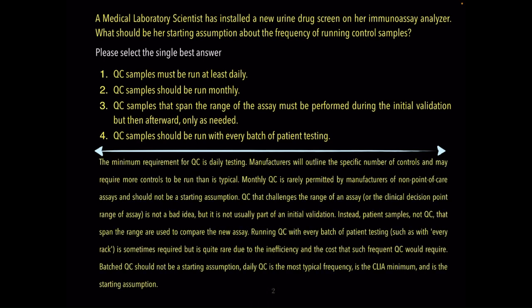The correct answer. The minimum requirement for QC is daily testing. Manufacturers will outline the specific number of controls and may require more controls to be run than is typical. Monthly QC is rarely permitted by manufacturers of non-point-of-care assays and should not be a starting assumption. QC that challenges the range of an assay, or the clinical decision point range of assay, is not a bad idea, but it is not usually part of an initial validation. Instead, patient samples, not QC, that span the range are used to compare the new assay.